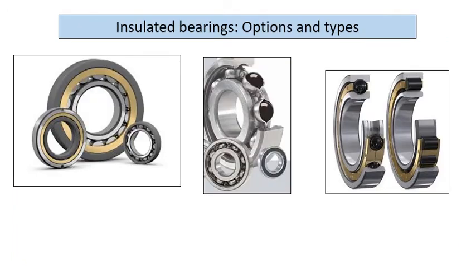And here, very important, I think someone even mentioned it earlier when we were chatting, quite often you have this fantastic insulated bearing, insulated this, insulated that, and someone goes and puts a lube oil pipe onto the bearing and it's solid steel. Or they replace a bearing RTD that previously had an insulated tip and that touches the bearing. It's very common. I see Fani nodding his head, so be careful with that.